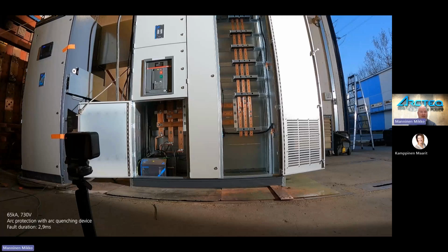But when you want to protect, and of course, I always want to protect, then you need a fully functional circuit breaker and correct wiring and so on. So we are tripping the breaker, but simultaneously we are also sending a coded fiber optic message to this device here. This is called arc quenching device, and it is a device which can be reactivated. And you can focus on these points where the arc is ignited and where the arc quenching is operating. So I will play the video now. It will probably play a few times because it's quite fast. So you can see the activation and reaction here. So let's go with this.